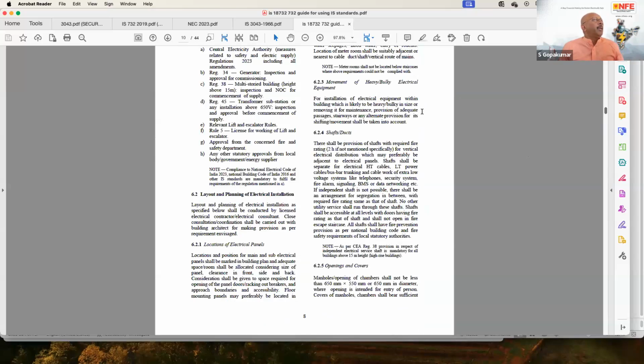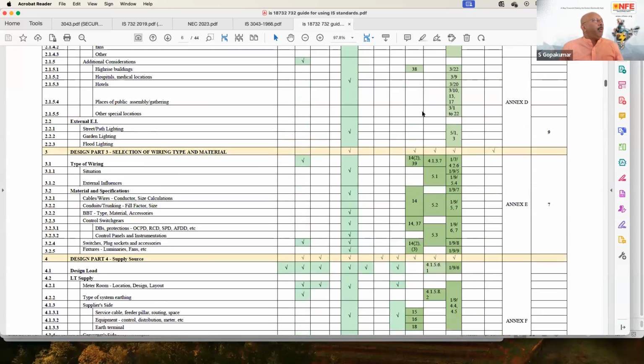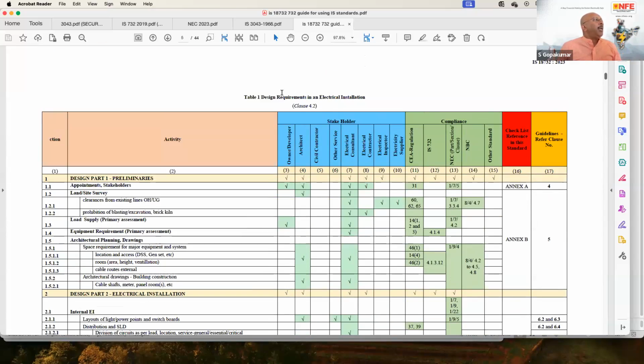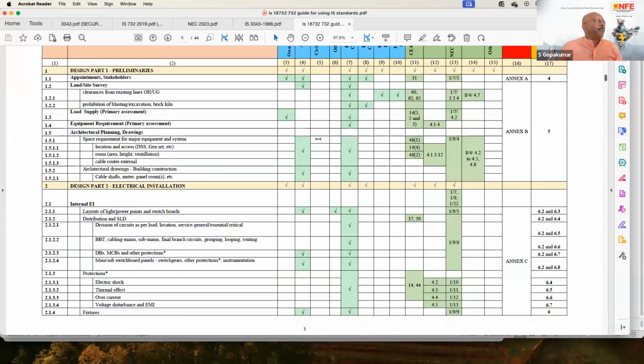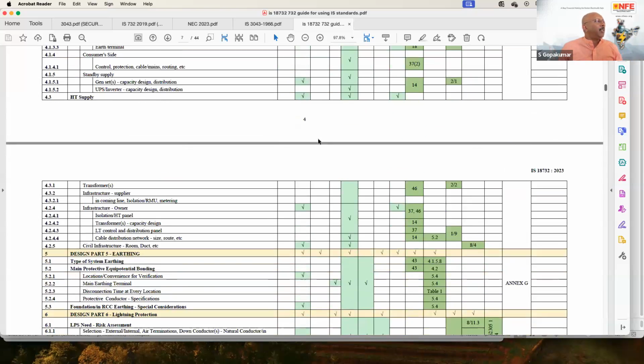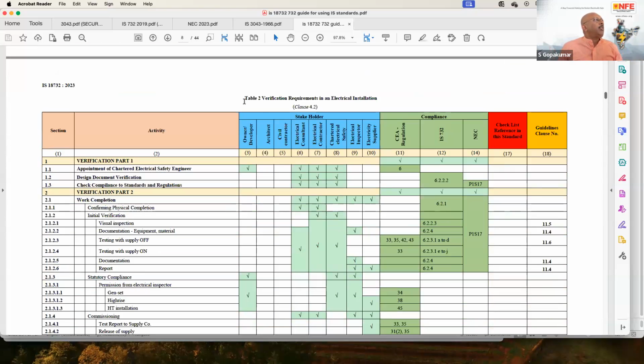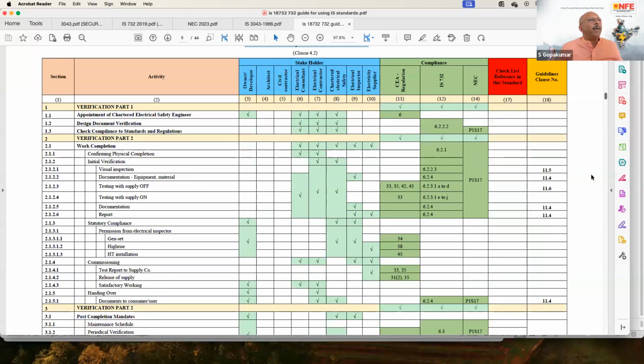Now, we have 2 tables. Table number 1 explains the design requirements in an electrical installation. Design and selection, I would say. Table number 2 talks about verification requirements in an electrical installation. Verification is nothing but inspection and testing. So here it explains who has to do what and where these things are explained. All the standards applicable for this particular verification have been captured.